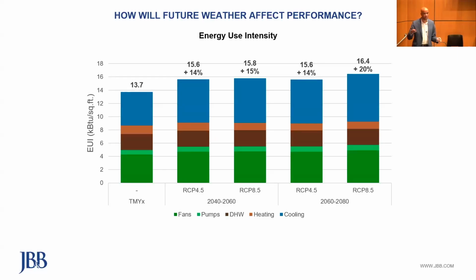And this is where I'm going to call back to the description I was giving you of the overall heating and cooling plant, because while this is, we think, very emblematic of the buildings that New York City is promoting, it is also very different from a lot of the buildings that exist in New York City. With a 4-pipe air source heat pump system, this building is getting something like 3 times the efficiency of a typical gas or steam central plant system in terms of just the coefficient of performance of the equipment.